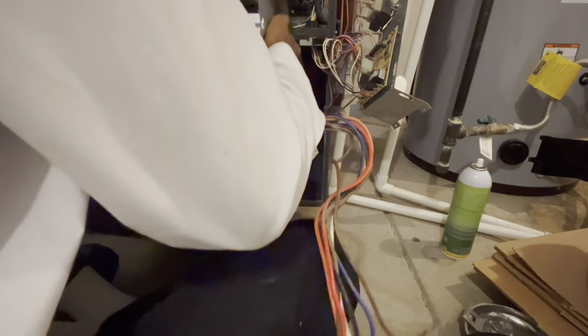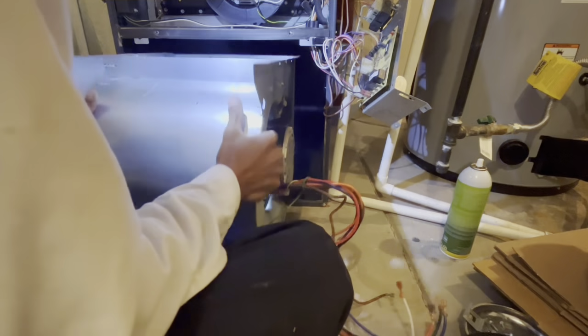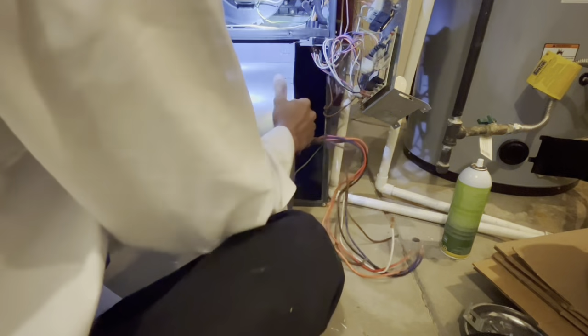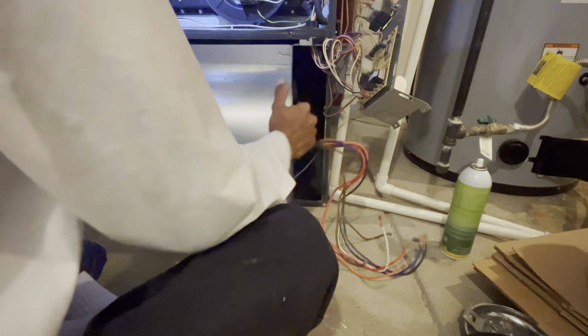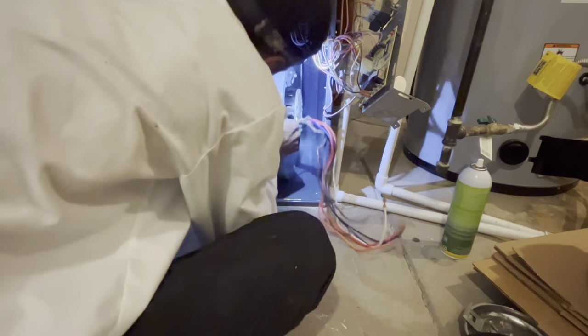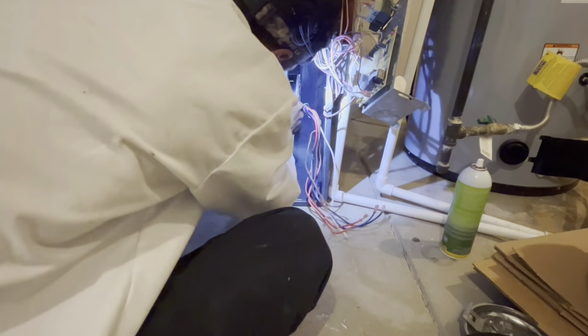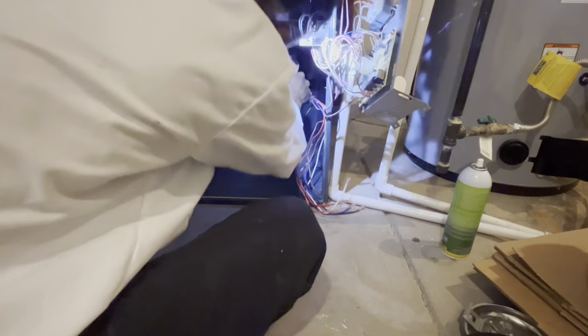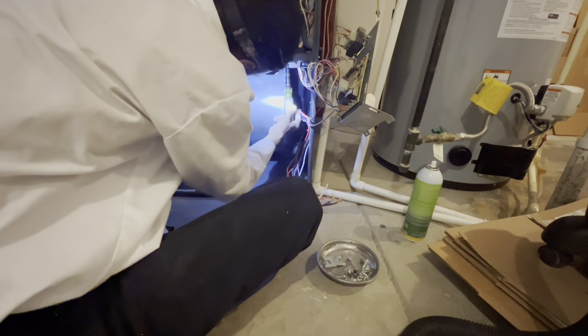These factory motors are only set up to spin in one direction. You have to be careful if you are purchasing a universal blower motor. You can have a blower motor that can go in two directions, and you will find that it will have additional wiring onto that blower motor, different colors, like an orange color and maybe a red color, and there'll be shorter wires, and they'll be basically tapped together to themselves, and you can make the rotation of that blower motor go in a different direction.